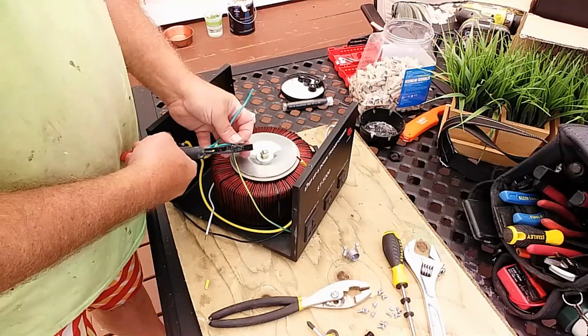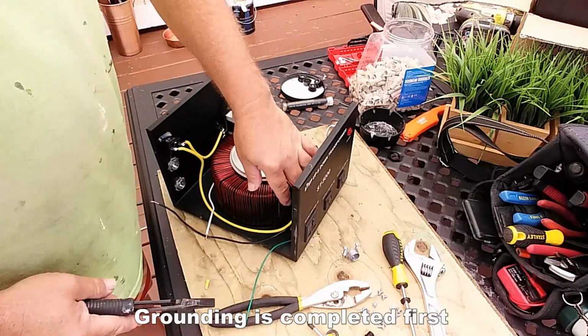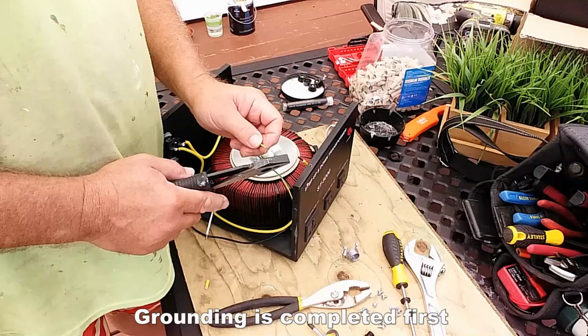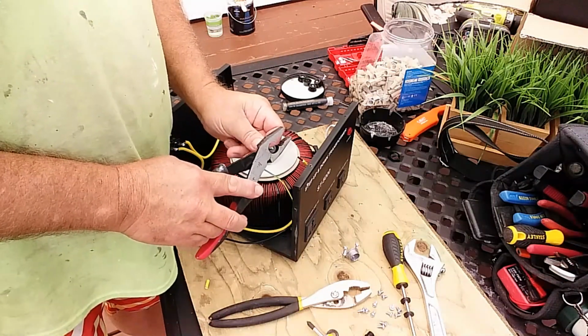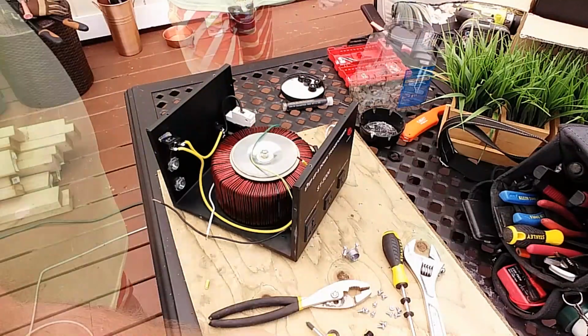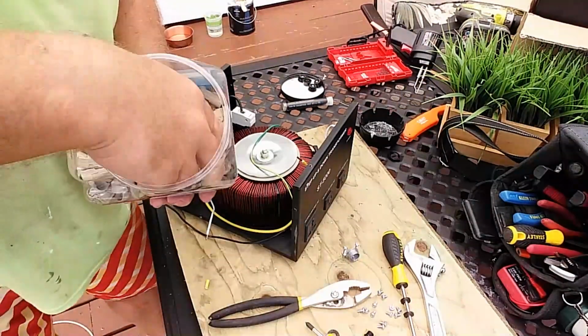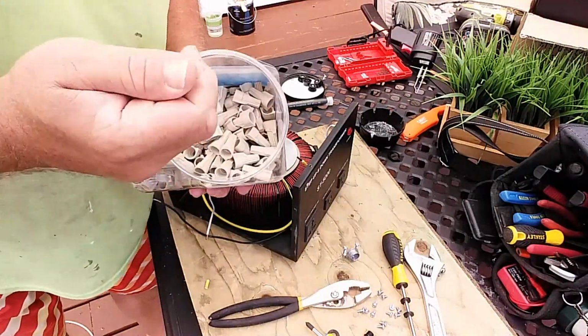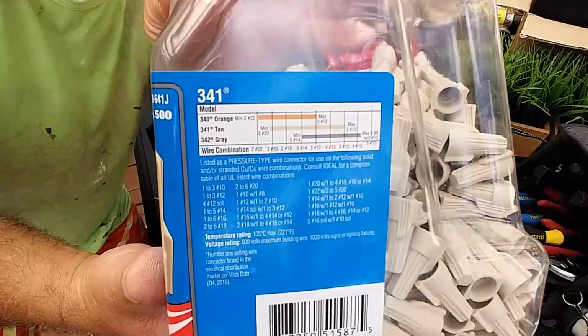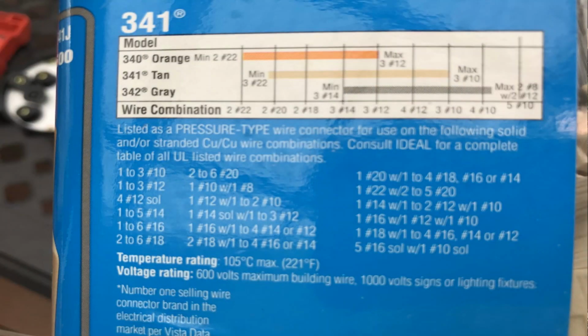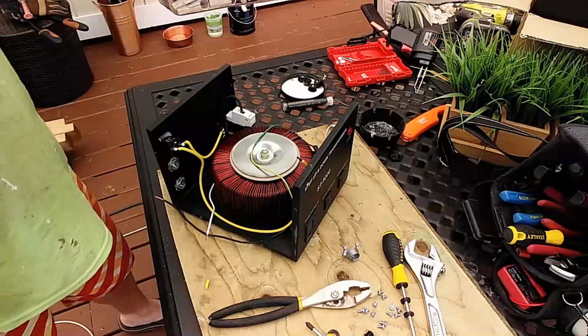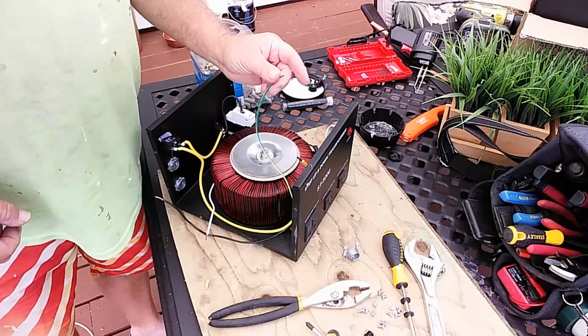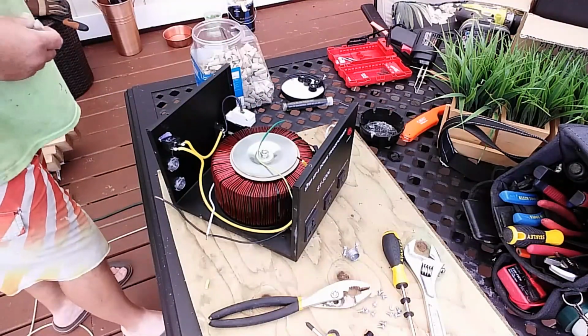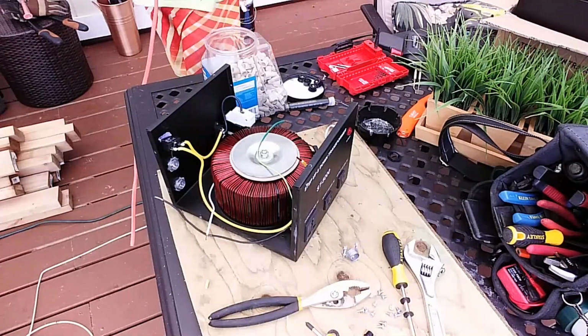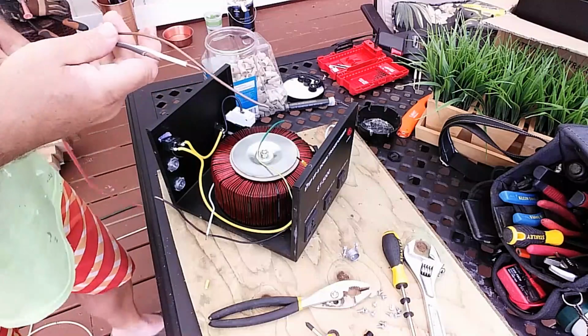I'm not going to need that little eyelet thing anymore. Now, I usually use these little tan wire nuts here to make my wire connections. You can see here that it's good for up to 3 10-gauge connections. We're only going to make 2 10-gauge plus maybe 1 14-gauge, except in the case of the ground, which would be about an 18-gauge, maybe a 16. And I use all 10-gauge wire for my connections.